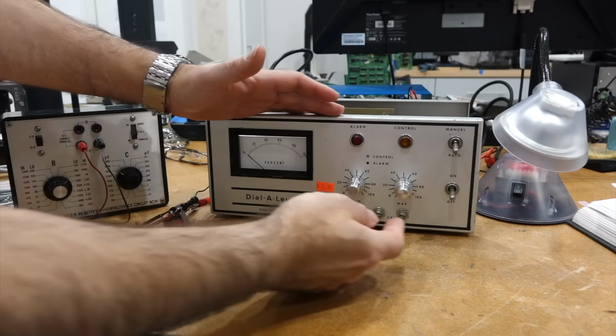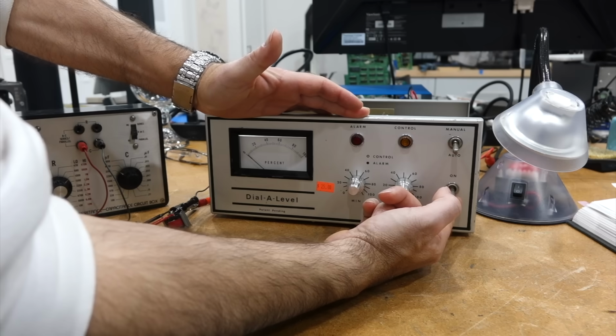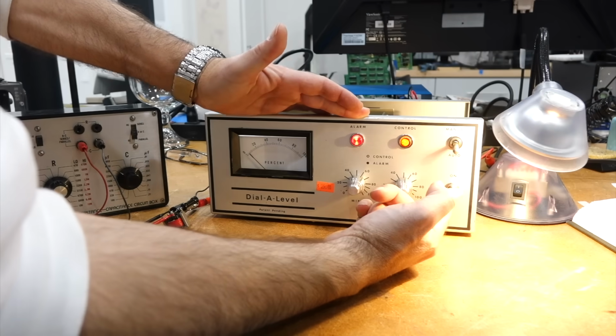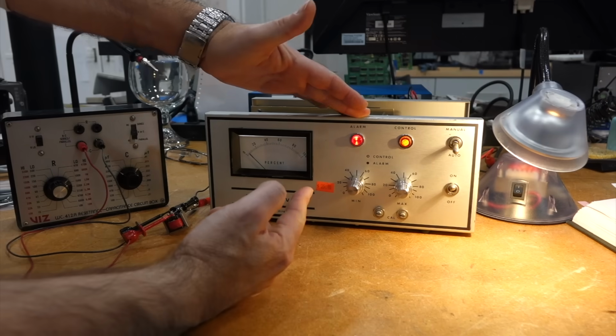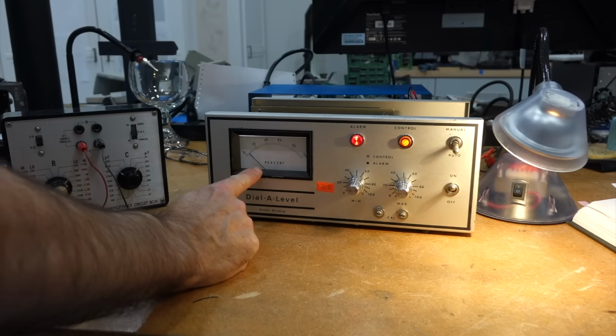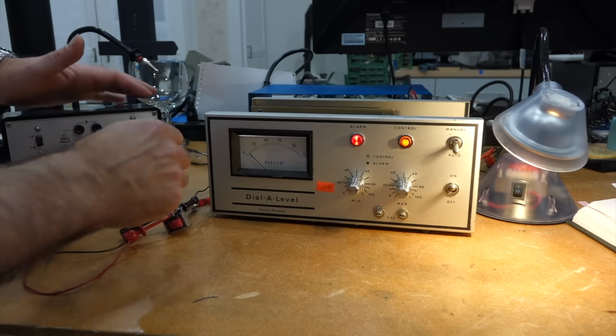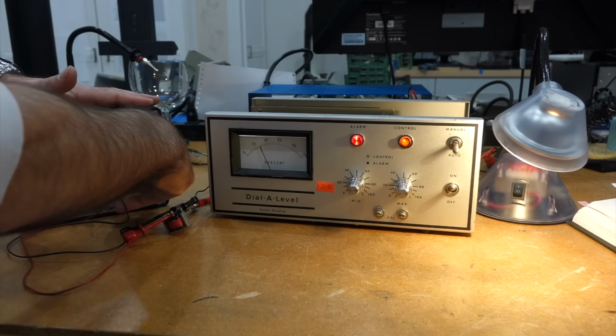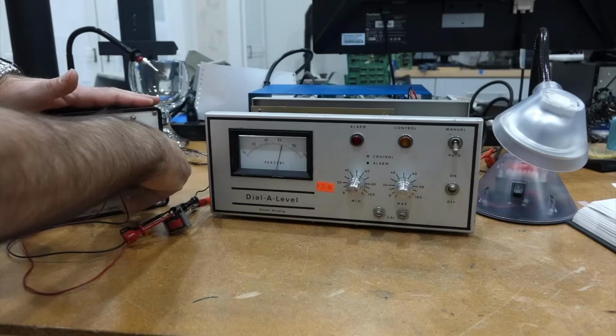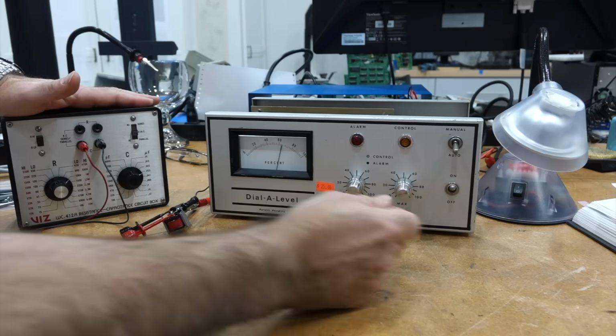And let's try it again. Now I have hooked up the lamp as the load, so we'll see if the triac works and if I can control it. It sure does. It turned it on because we're low, so we're below the minimum. So it turned the lamp on. That's correct. And now I am going to go up. And it went past the maximum and turned the lamp off. And then if I go back down, it needs to go below the minimum to turn it back on. So we have the two SCRs playing flip-flop with each other, which creates that programmable deadband.